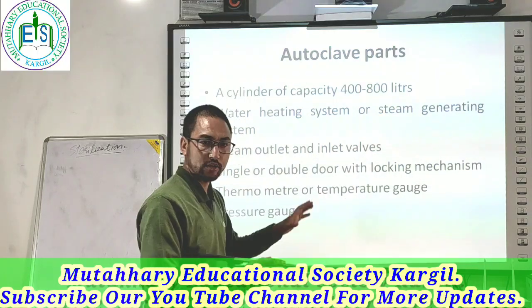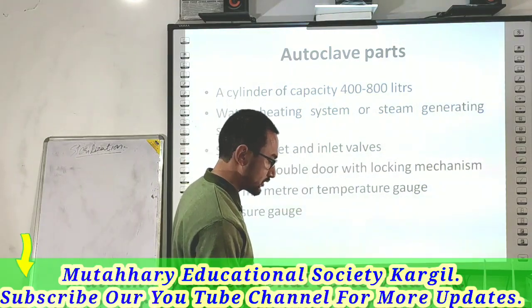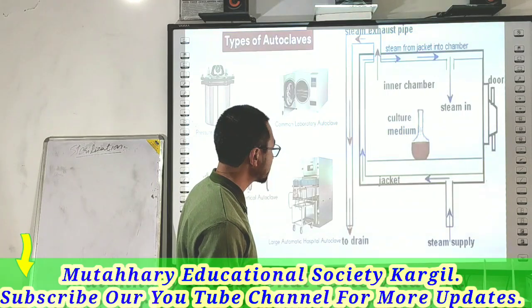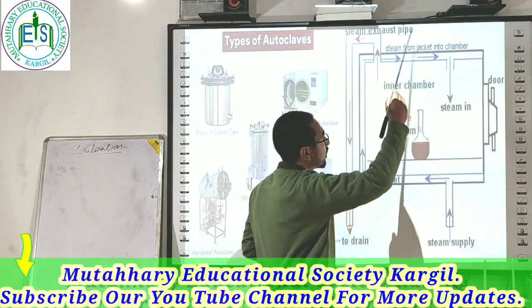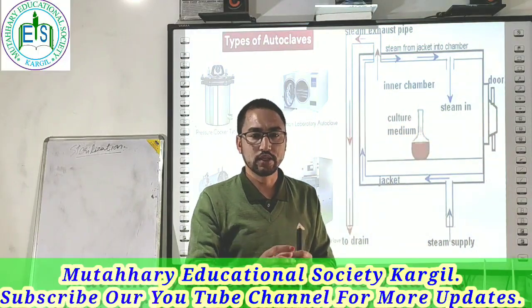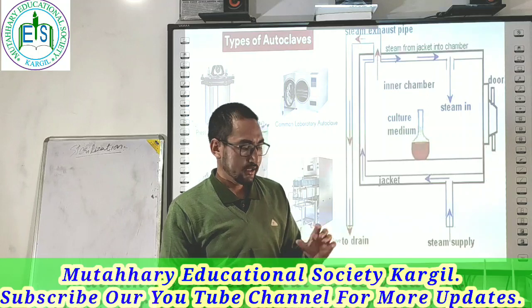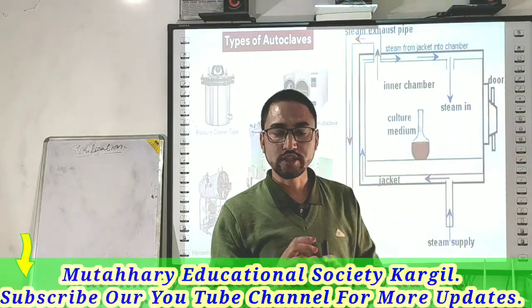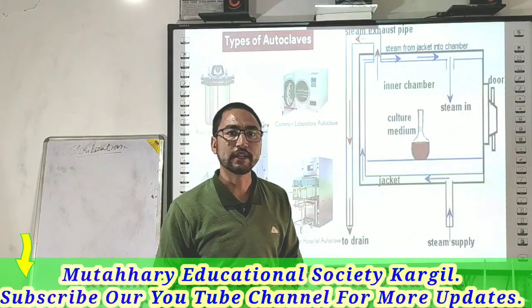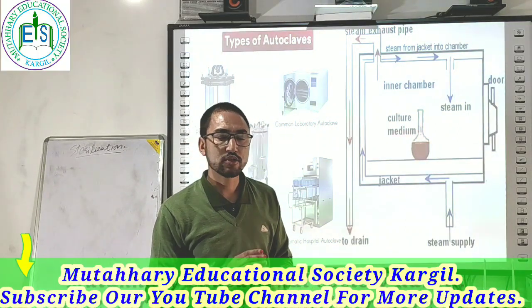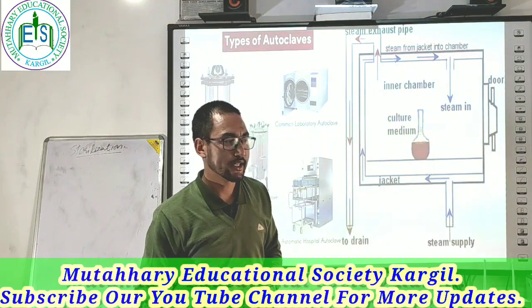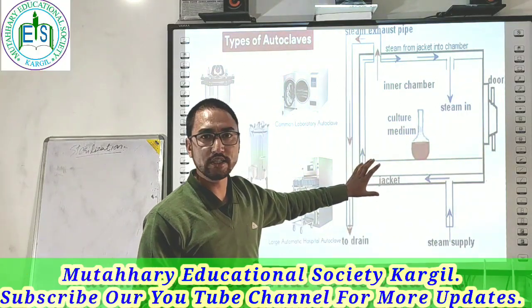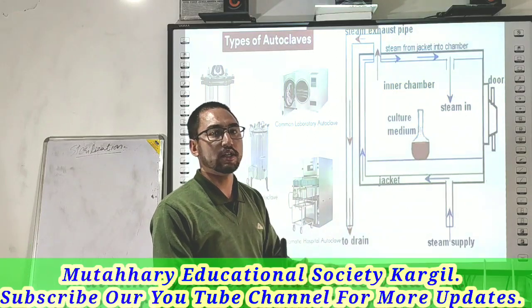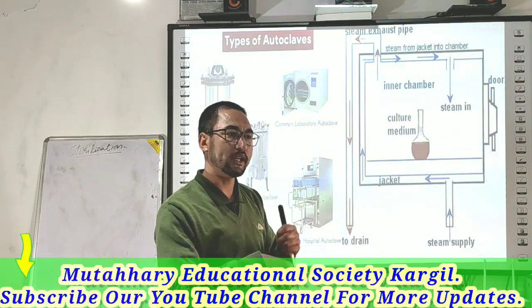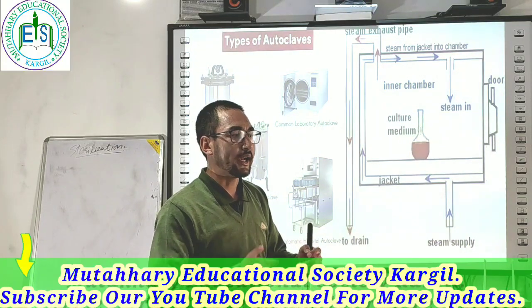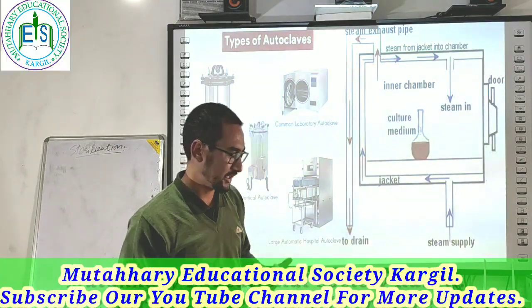You have single door and double door, which I have already discussed. There are a thermometer gauge and a pressure gauge. These are very important things. Somewhere here you have two knobs, and from there you can easily read the temperature and the pressure. The gauge which tells the pressure should be maintained at 15 psi, and the temperature should be at 121 degrees Celsius. There are also digital autoclaves, where you can set the time, and after a certain time interval it automatically switches off, and when it cools down we take all our materials outside.